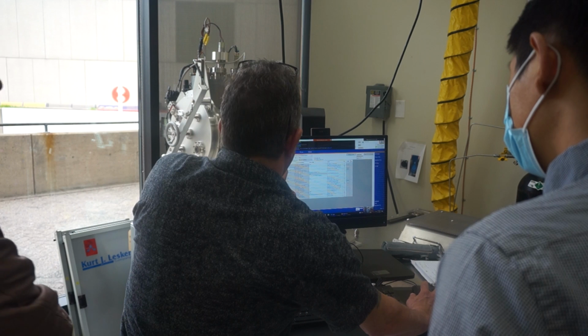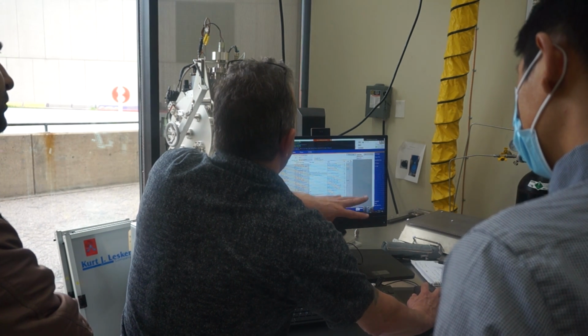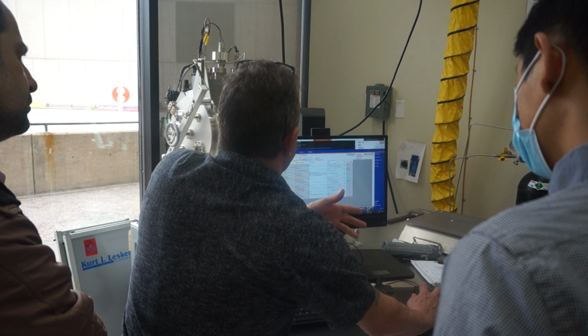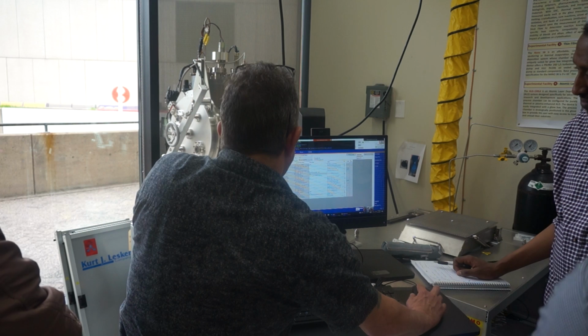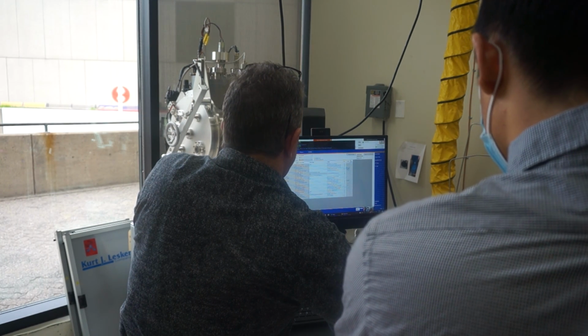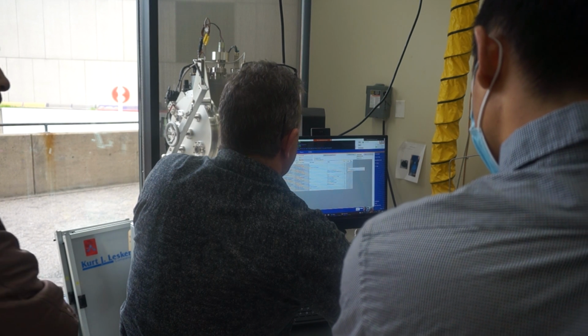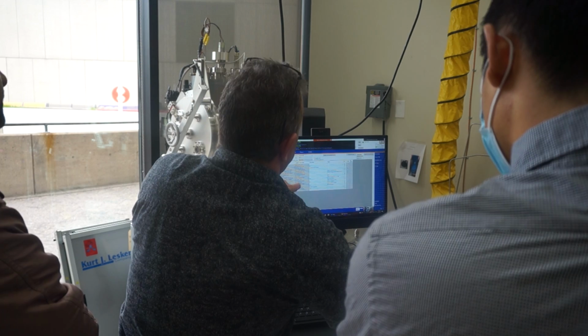Then it sets an abort recipe. What do I want the system to do if things don't go as planned? That's just the abort process recipe. Then it runs a sub-recipe for the gas flow, which we've run a few times now. This sets your gas flow for your process chamber and your source gases.